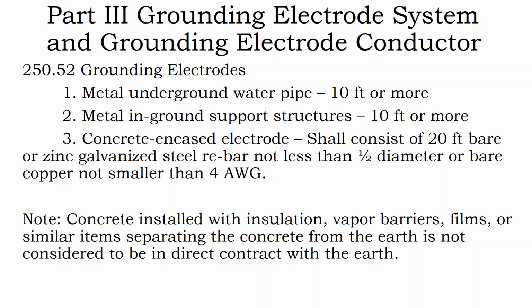And so what constitutes a grounding electrode? Well, there's a few things that do. A metal in-ground support structure. That could be like a pile. So you're driving a pile from your solar ground mount into the ground. Well, guess what? Most solar piles do not have 10 feet or more of depth into ground. So when you're driving a pile into the ground, that commonly does not qualify as a grounding electrode, even though you think, well, certainly this pile is grounded.